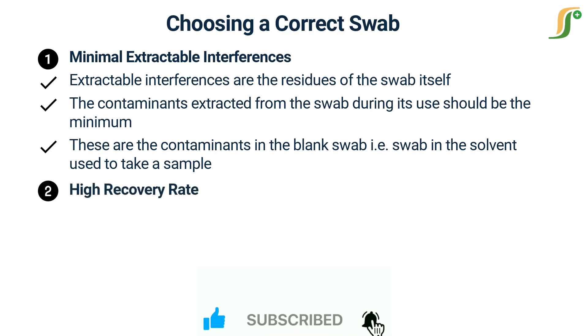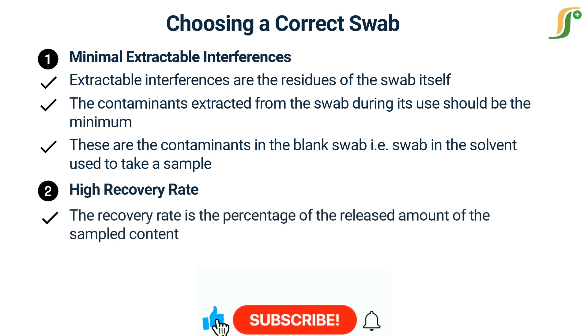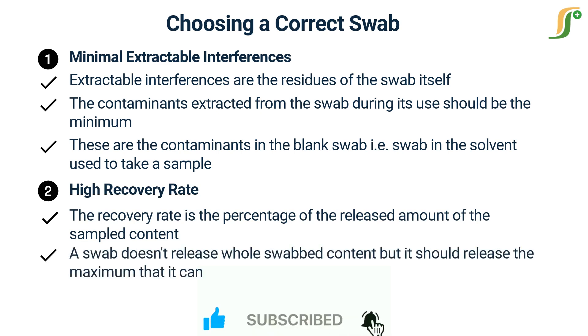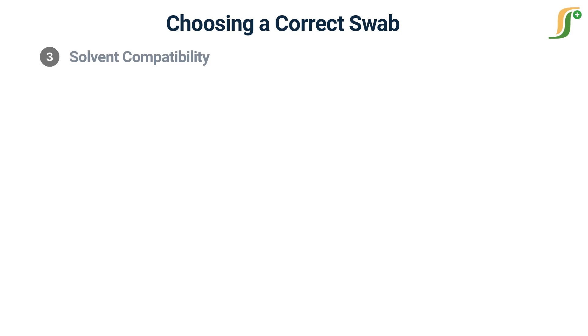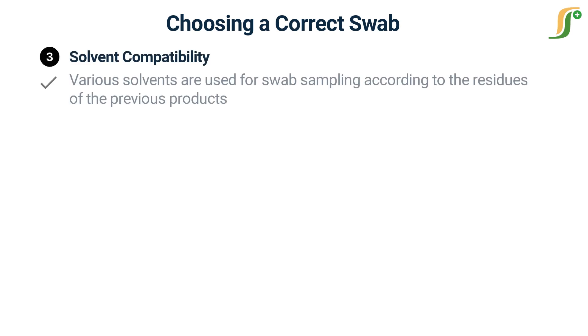Second is high recovery rate. The recovery rate is the percentage of the released amount of the sampled content. A swab doesn't release its whole content, but it should release the maximum that it can. A minimum 60% recovery rate is acceptable, but a higher recovery rate is better.